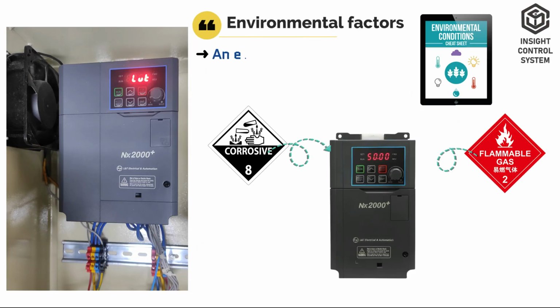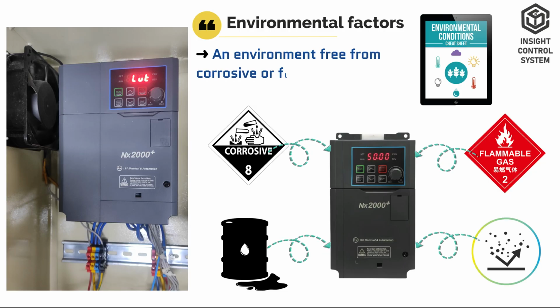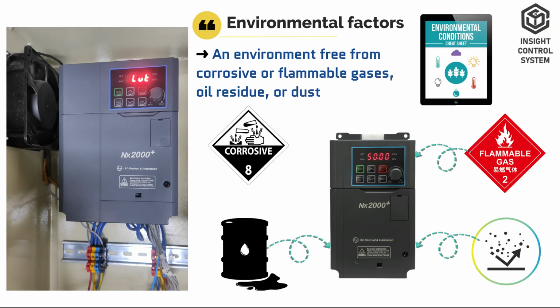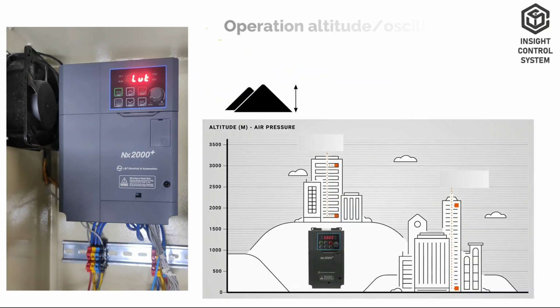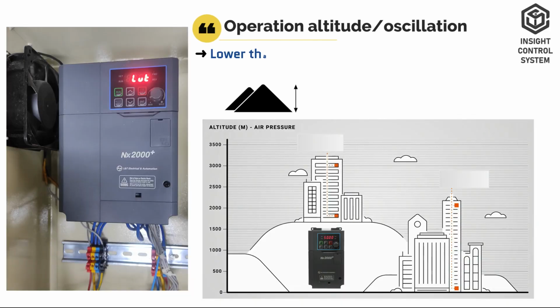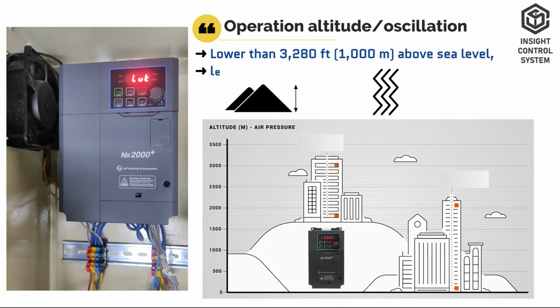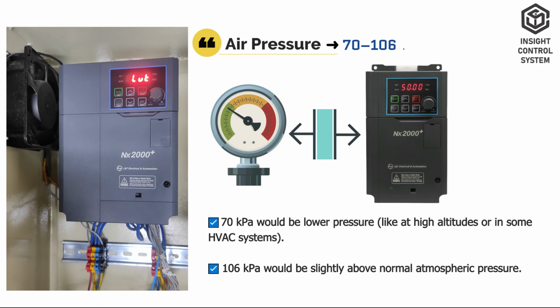Environmental factors. In an environment free from corrosive or flammable gases, oil residue, or dust. Operation altitude is lower than 3,280 feet above sea level. Operation oscillation is less than 1 G, that is 9.8 meters per second squared. Air pressure is minimum 70 to maximum 106 kilopascals.